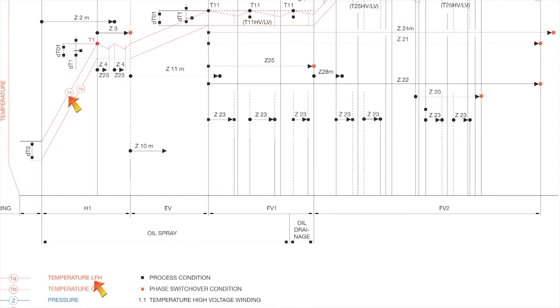The aim of the stabilization phase is to remove as much water from the insulation as possible at a relatively low temperature. In order to guarantee optimized drying results, the transformer tank will be evacuated during a certain time, Z23, without heating. And then the winding will be intermittently heated again with LFH current. This assures a better drying quality and reduces the overall drying time.